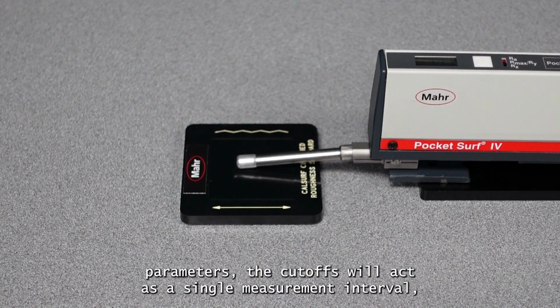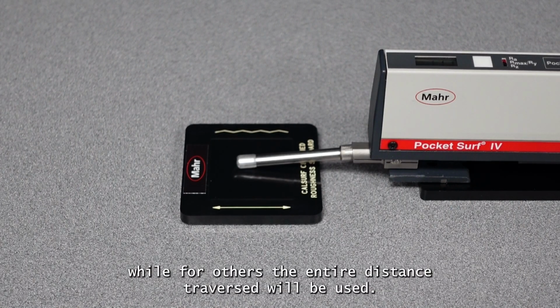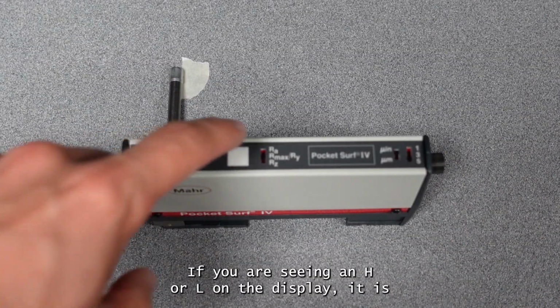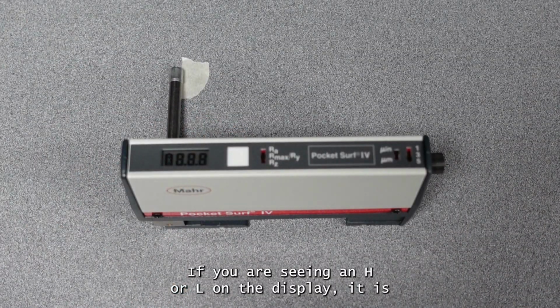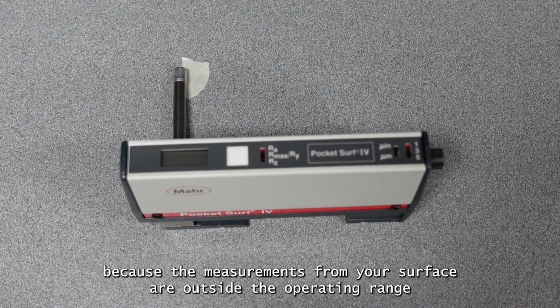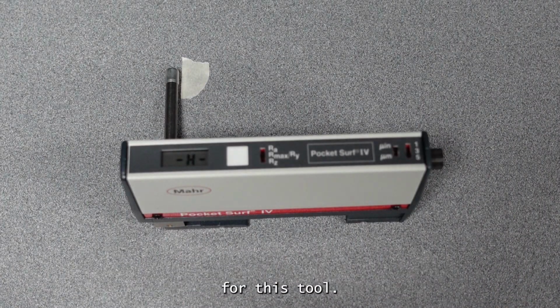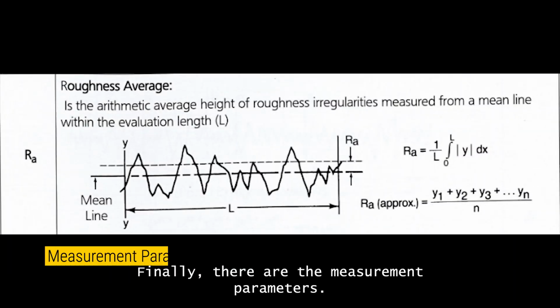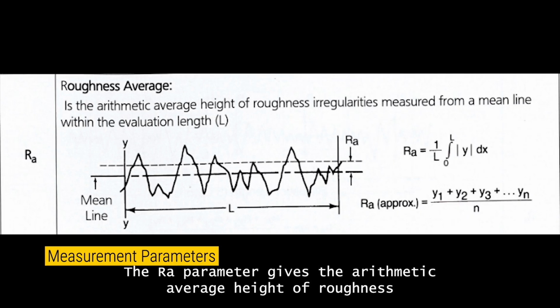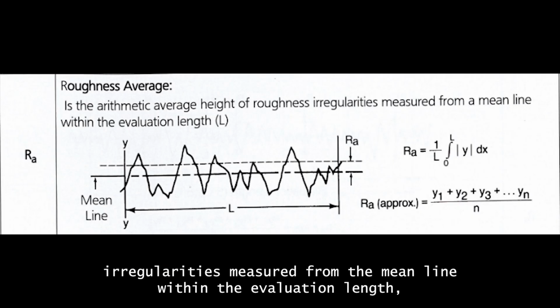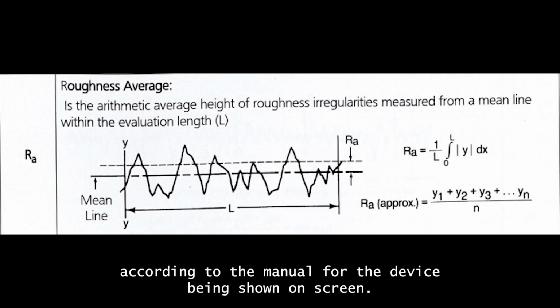For some measurement parameters, the cutoffs will act as a single measurement interval, while for others, the entire distance traversed will be used. If you are seeing an H or L on the display, it is because the measurements from your surface are outside the operating range for this tool. Finally, there are the measurement parameters. The RA parameter gives the arithmetic average height of roughness irregularities measured from the mean line within the evaluation length, according to the manual for the device being shown on screen.